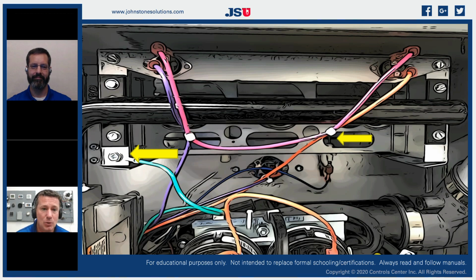So we need to make sure when we're cleaning these flame rods, we're also inspecting that ground wire, removing that screw, rubbing it down with a little bit of sandcloth or wire, putting that back in and making sure to measure our microamps. Because we had, not very long ago, a contractor in one of our other states. He put 5 boards on a furnace, all under warranty. He said, hey, what's going on with this? I said, well, let's take the board and let's go check it out.